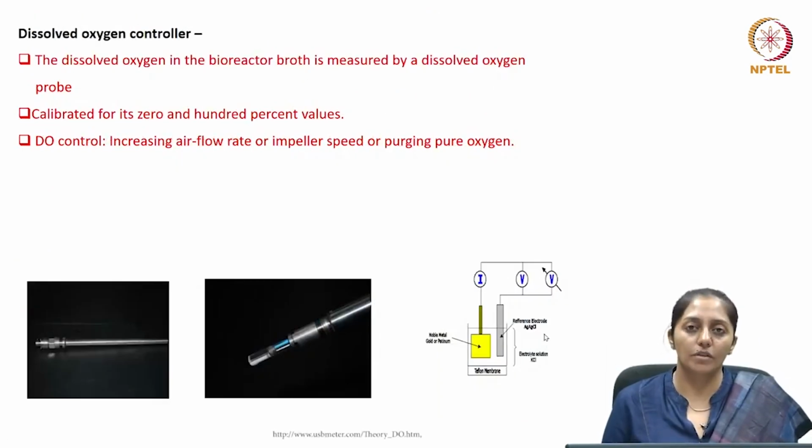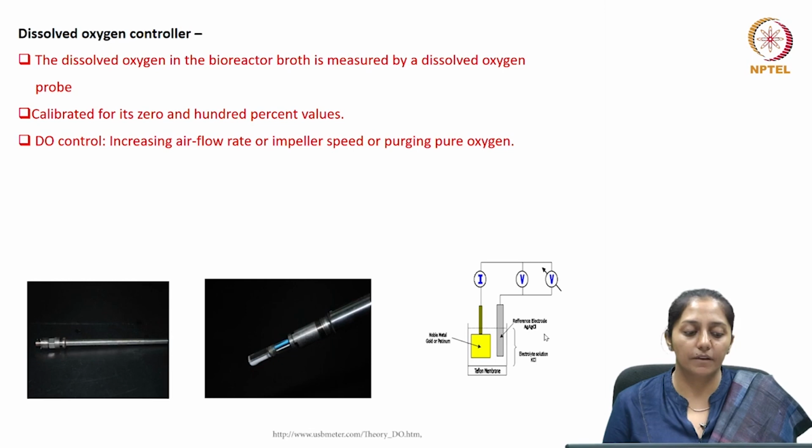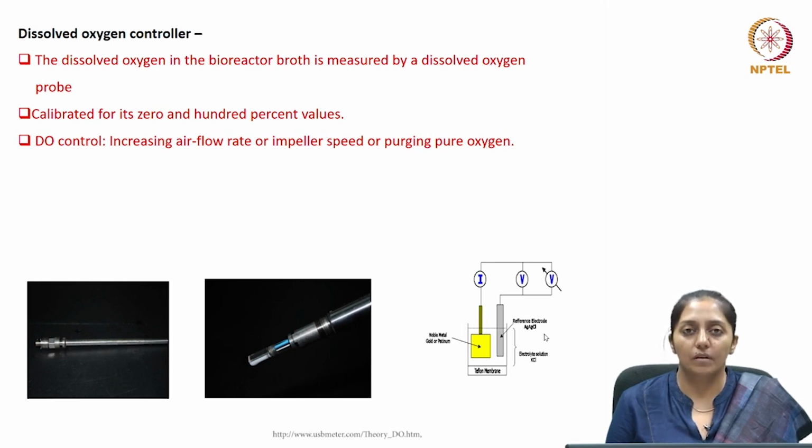Then talking about the dissolved oxygen probe. The dissolved oxygen in the reactor broth is measured by a dissolved oxygen probe. It is based on the principle of galvanic or polarographic electrodes. The schematic here shows a polarographic electrode where the membrane at the bottom is selectively permeable to oxygen, and the oxygen gets reduced at the noble metal electrode, due to which a current flows, and it is measured as proportional to the oxygen tension of the broth.